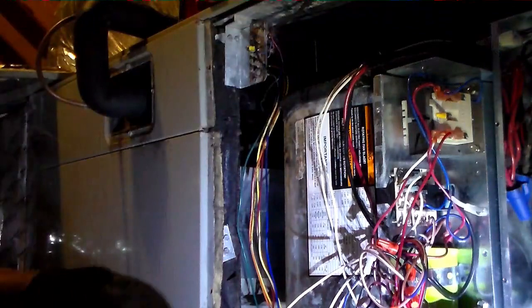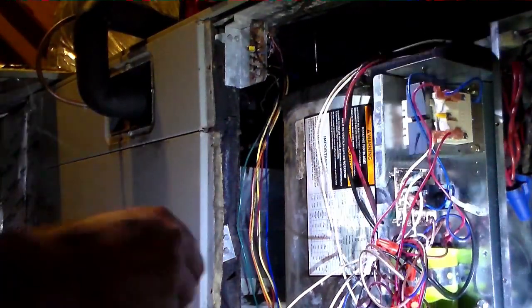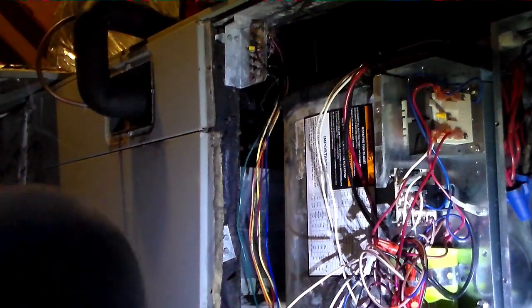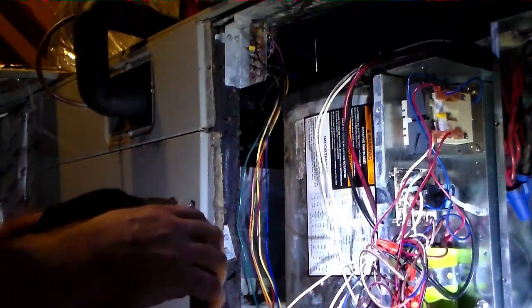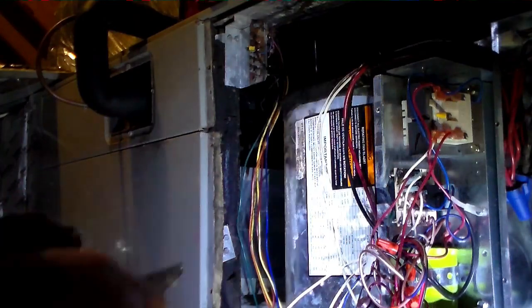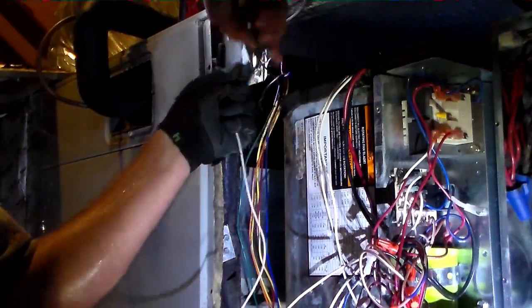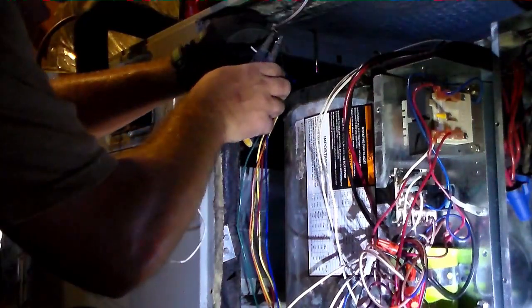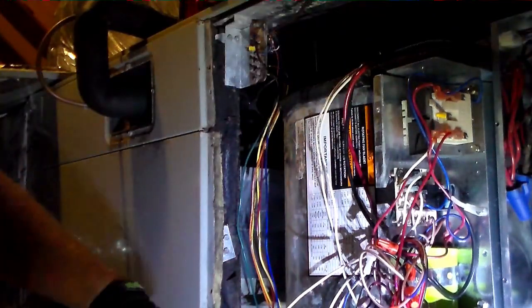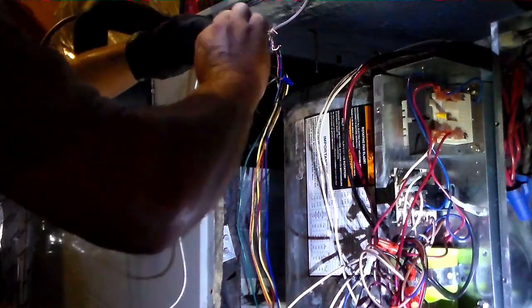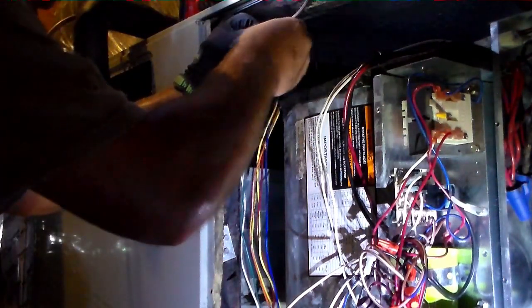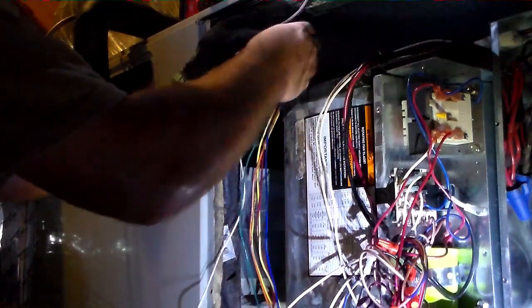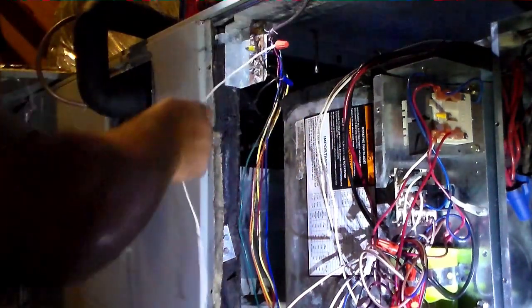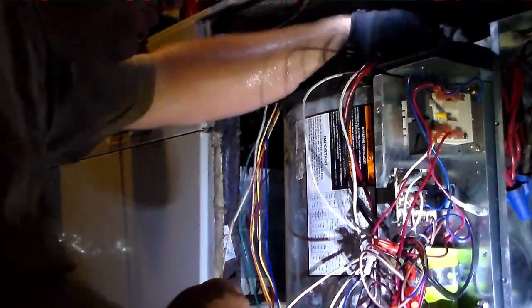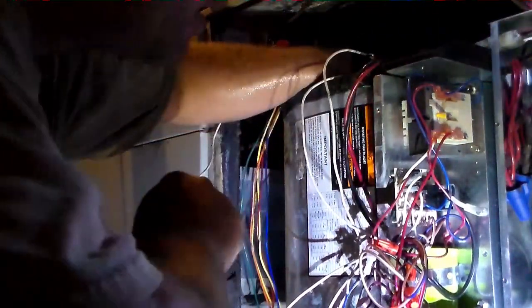And then I can put a wire nut on it and run it over to the white for the heat kit and go directly to it. Cut out that old copper there so it doesn't snap off. Good, nice fresh section of copper wire. We can take it here, and we'll go to top and bottom. Top goes back there, bottom goes.